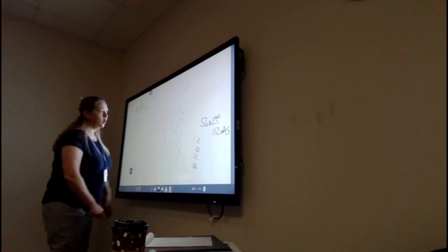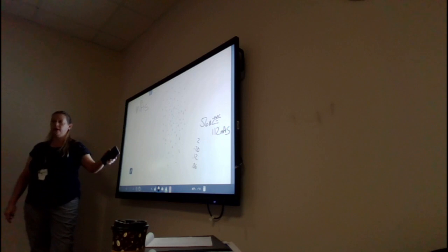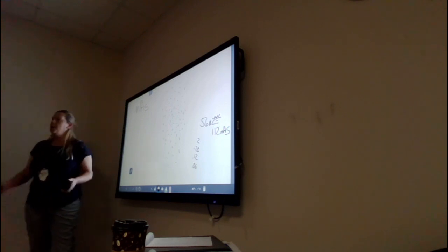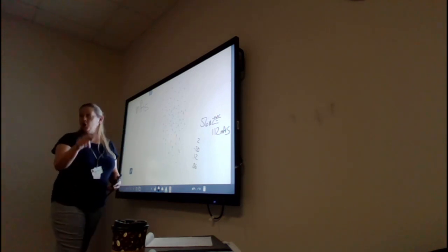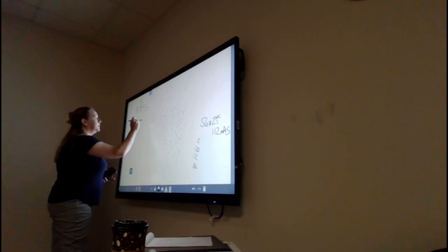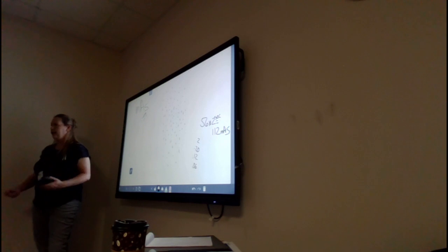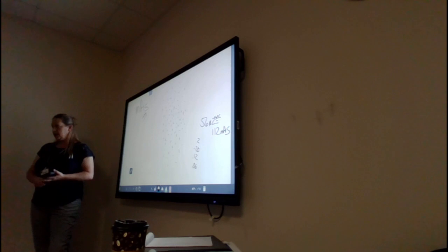So we can have a defined number of X-ray photons that we are creating. 56, 56 all day long. But it's how long I sit on that rotor, how long I sit on the second button, that can determine how many actual X-rays go. Does that make sense? Yeah, that's what Matthew was saying yesterday. You gotta hold it down. Press halfway to rotor it, and that's actually just spinning up the anode.